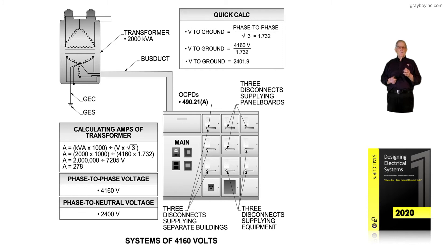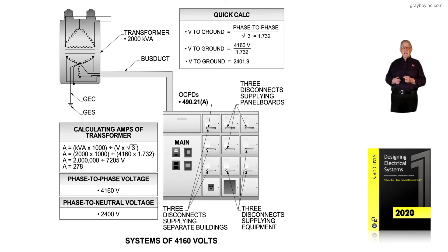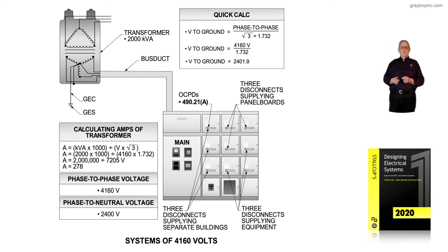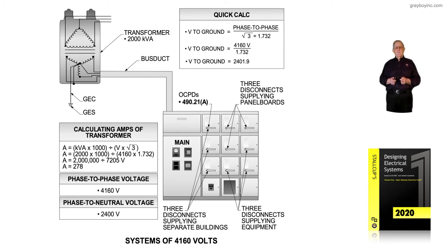...divide that into 2000 kVA times 1000, and we come up with 278 amps on those conductors — notice the smaller conductor sizes that could be used. You take 278 amps, round that up, that's a 300-amp main to carry the full 278 amps, or round it down to 250 and protect everything within the switchgear.